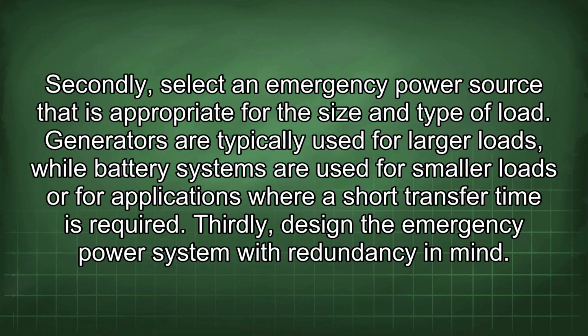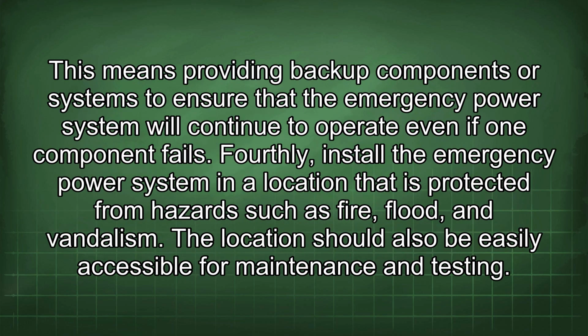Thirdly, design the emergency power system with redundancy in mind. This means providing backup components or systems to ensure that the emergency power system will continue to operate even if one component fails. Fourthly, install the emergency power system in a location that is protected from hazards such as fire, flood, and vandalism. The location should also be easily accessible for maintenance and testing.